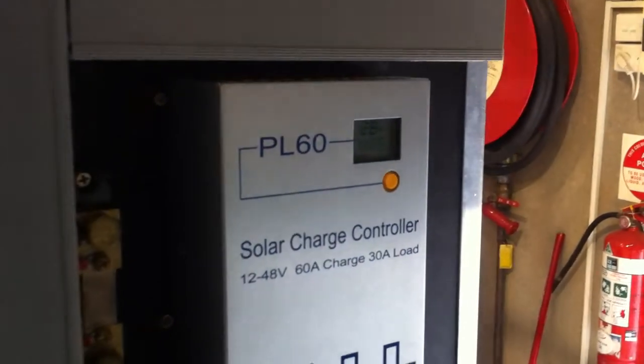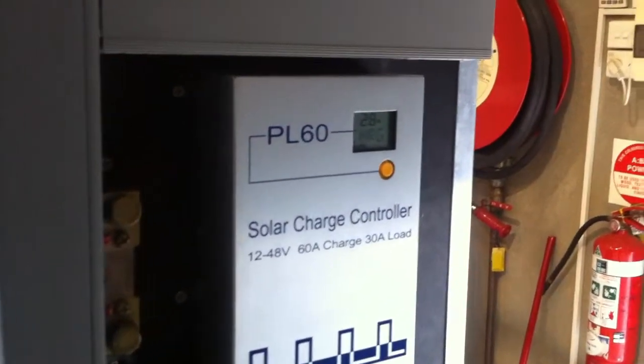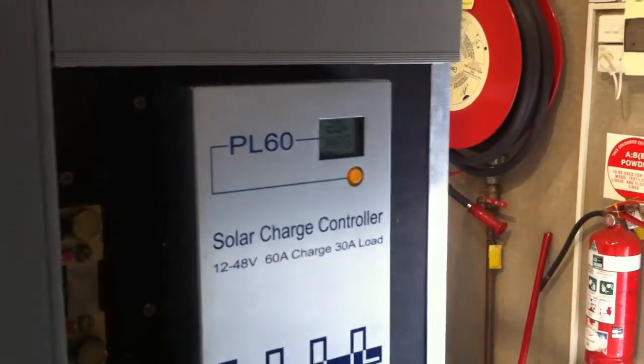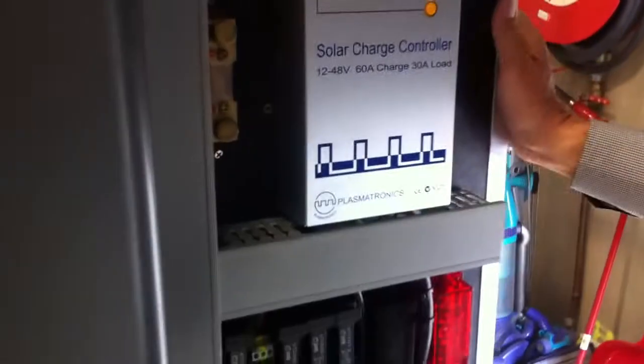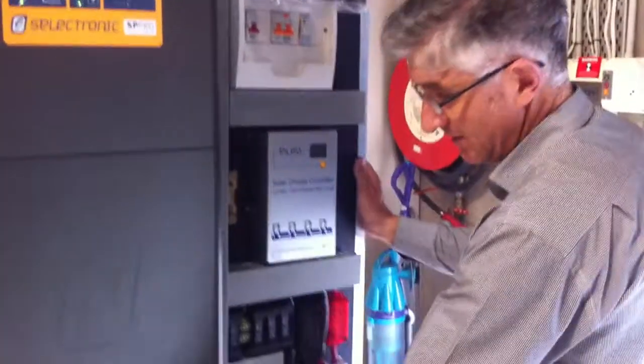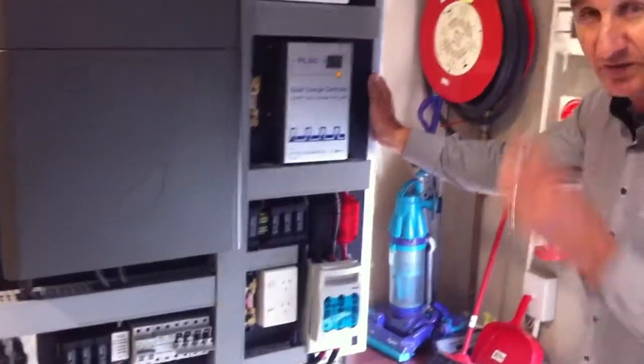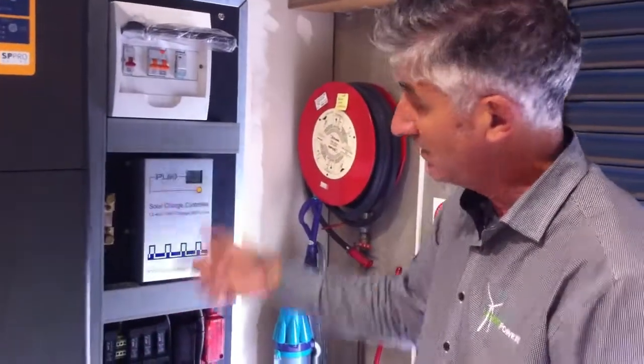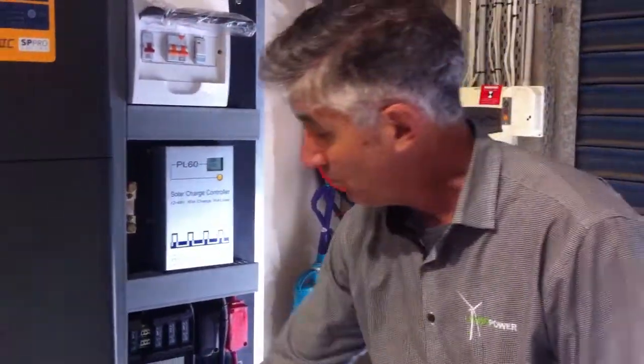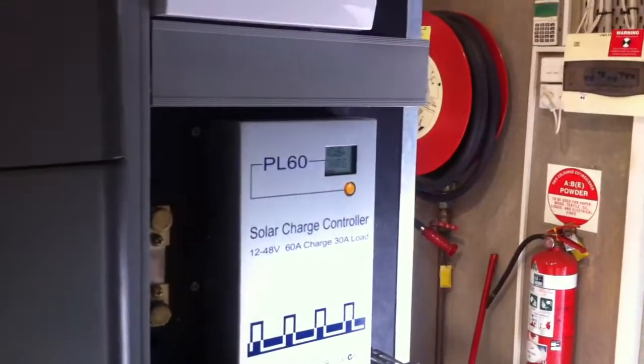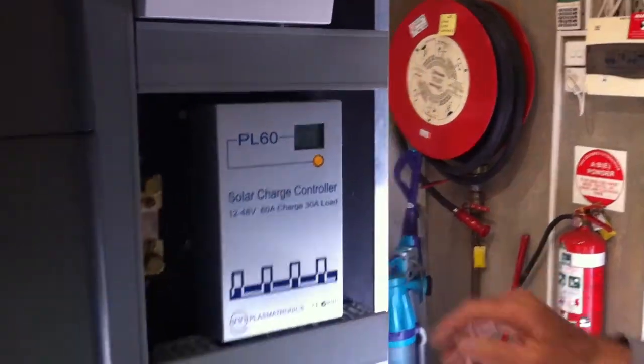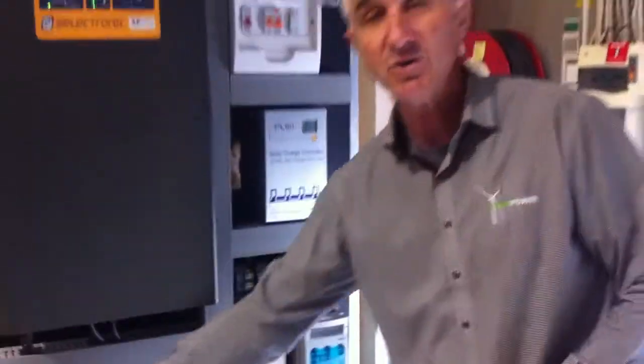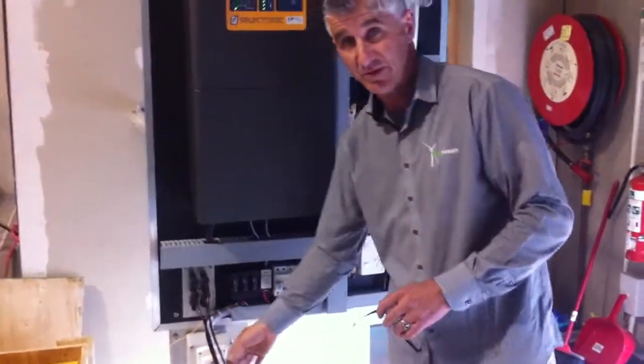It's really important to check by pulling out one of these fuses - have a look, I've just pulled one fuse out, but I've still got some charge going in. Then if I pull that one out, it drops right off, so there's no charge. What we've done is check one string cable at a time to make sure each one is actually working, in other words that you don't have a loose connection on the roof. Either pull one out at a time and see it change, or push one in at a time - you might start at 2 amps, then push another string in and now you've got 4 amps of charge, obviously depending on the sunlight at the time. But it's important to make sure each one of these string cables is actually operating.